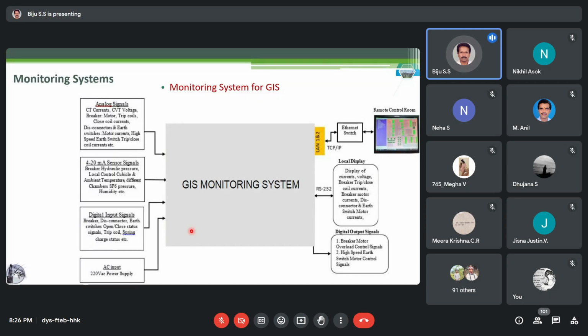Then again the hydraulic pressures, if it is hydraulic mechanism. If it is pneumatic, then the temperature, then the pressure, air pressure. If it is spring, then the motor charging currents. Those things will be monitored. Ambient temperature will be monitored. SF6 pressure, humidity will be monitored. Then again, it will display all the currents. Output will be all the values will be displayed in the dashboard, and any abnormality noticed in these measured values will be flagged out also.